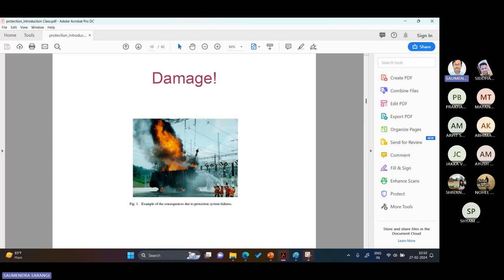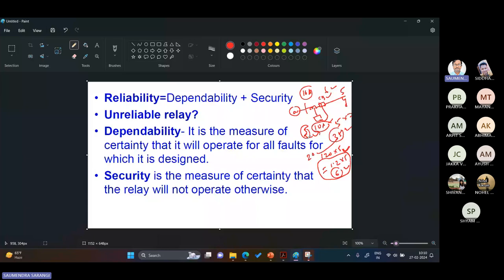So for that reason, we need to detect any type of fault, whatever fault occurs. That is why we always set the relay towards the load point, because you are observing two conditions: one is the fault current, the second is the load current. Even if we set it towards the load current, even a small change in the load current will be detected as a fault. Our relay will be detecting a false fault and reliability will be lost, but a fault going undetected will never happen.